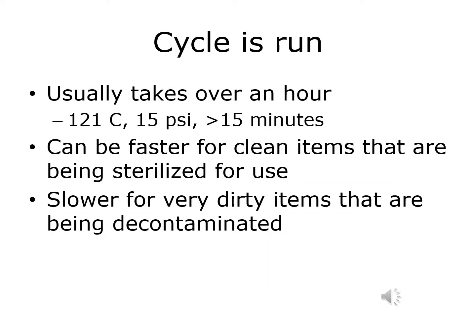This slide just outlines a very general way that an autoclave works, talking about the temperature and the pressure and the time. There are other choices to be made. You can sterilize faster or slower. It's probably not going to be your responsibility to determine what's in the autoclave and the parameters of the sterilization. But one thing you can know is that this often has an unpleasant odor. And so it's not that something has gone wrong, it's in fact something has happened correctly.